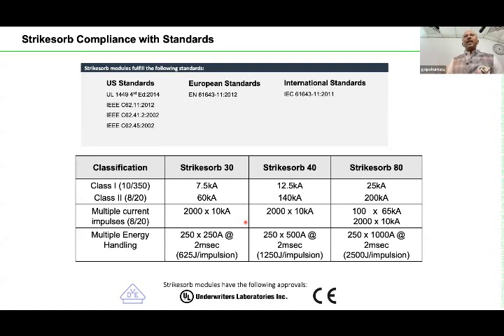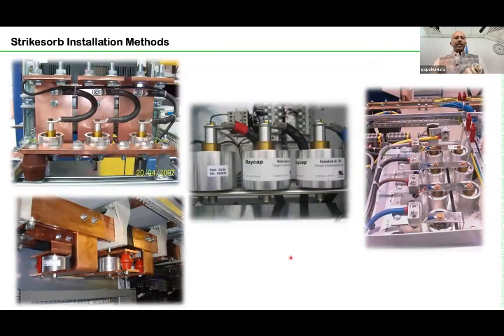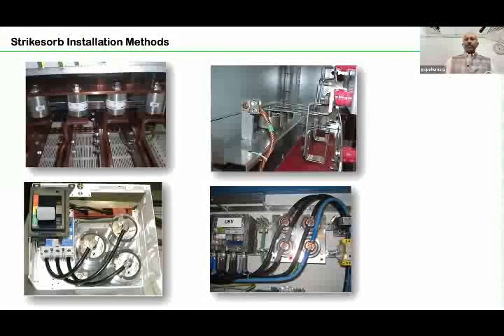So in such critical cases, if your installation is so critical, then you can go for this kind of bus bar mounted SPD, because these are tested for multiple strikes. Similarly, this is also tested for long duration strikes. I would say this is the only SPD which is tested for long duration strikes, because this is a non-standard test. The standard hasn't recommended this kind of test so far. Now, some installation examples. So the wire length and the selection of the SPD are very, very important.